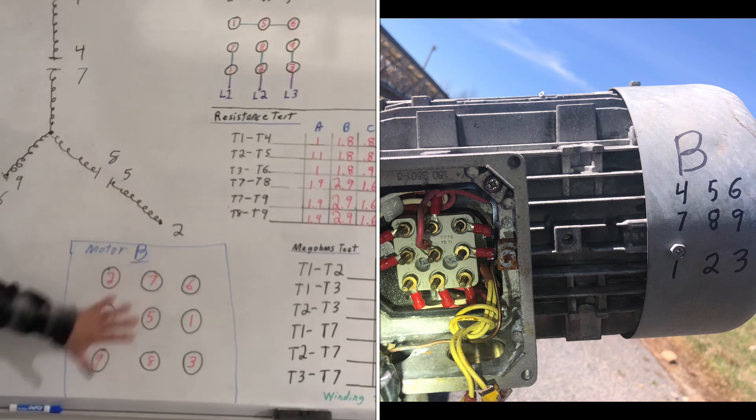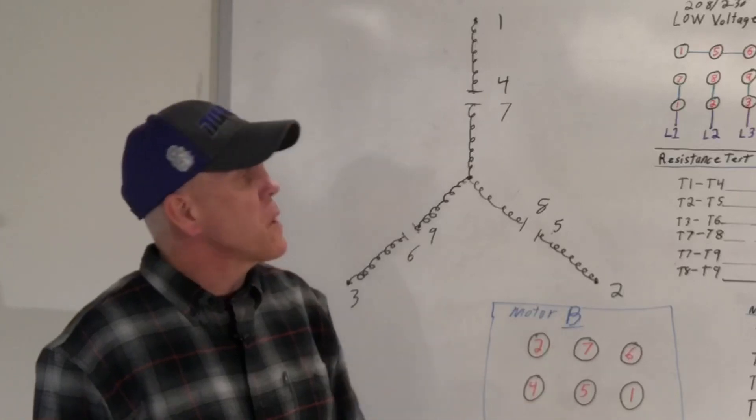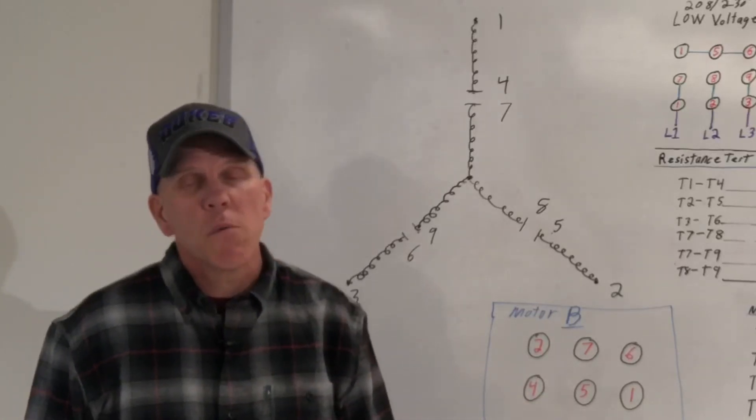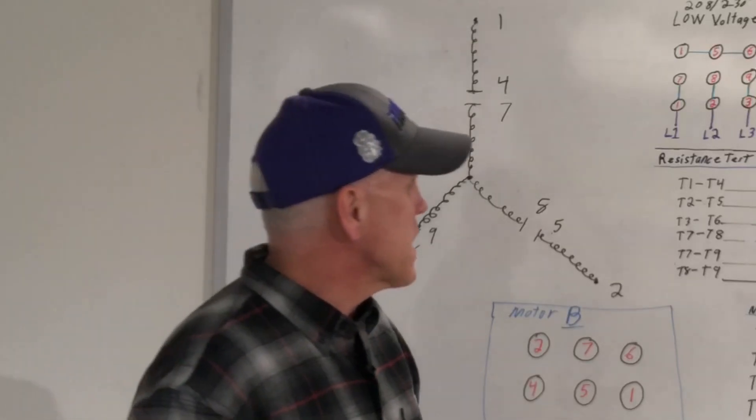I just pretty much turned it into that. But these are my readings I got. And it was kind of a burnt smell on that motor. So I will talk to the customer and see what they want to do about possibly getting that replaced.